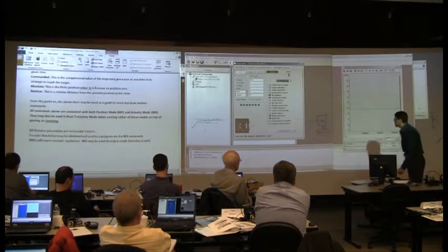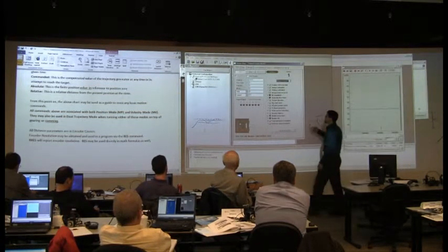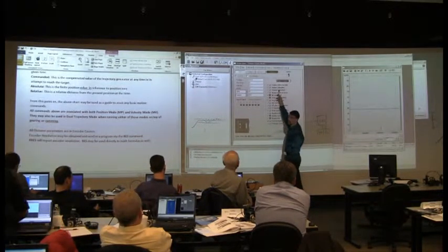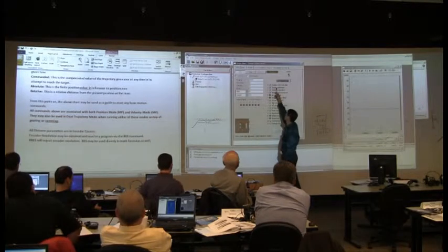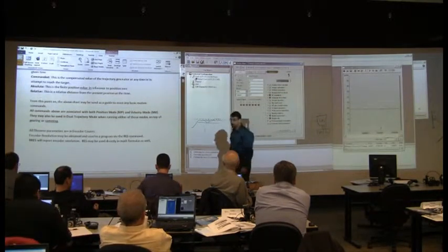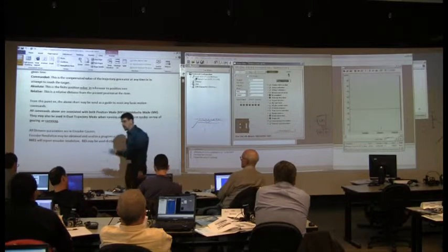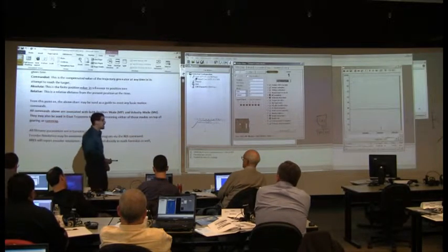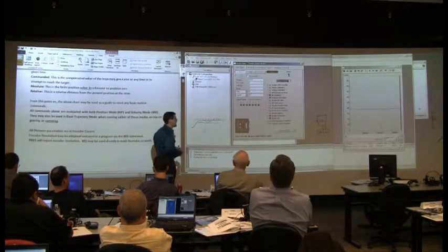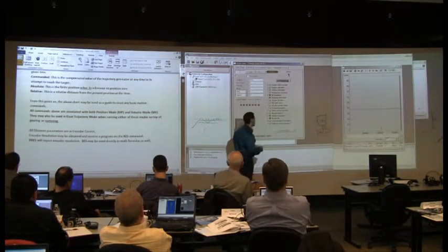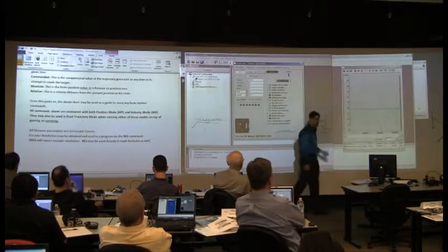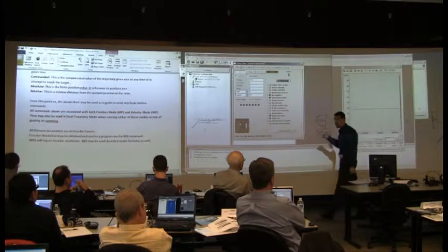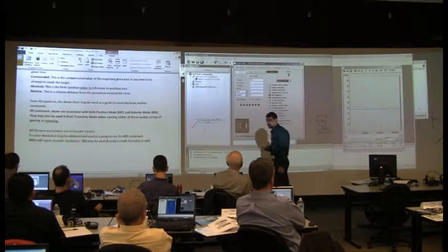Okay, we talk a little bit about this. Torque and voltage saturation. You're only getting voltage saturation in an AC product that we haven't yet delivered to the open public. Torque saturation, you can get on this one now. Torque saturation means for the given demand, you have saturated as much out of the PID filter as it can command to the drive as possible. It can't give any more. That torque saturation bit says I'm working as hard as I can. It in and of itself does not cause a fault. Okay?